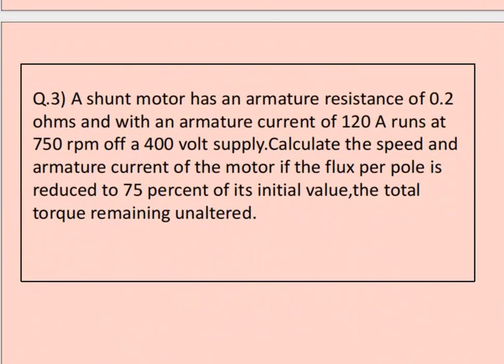Question number 3: a shunt motor has an armature resistance of 0.2 ohms and with an armature current of 120 amperes runs at 750 RPM off a 400-volt supply. Calculate the speed and armature current of the motor if the flux per pole is reduced to 75% of its initial value, with the total torque remaining unaltered.